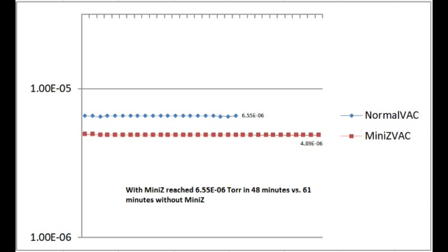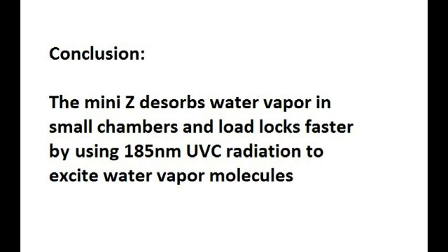Depending on your pumping, what type of pump you have, and the size of the chamber and other variables, it's going to determine what the net result is. But the conclusion is that the miniZ does in fact desorb water vapor in small chambers and load locks faster by using the 185 nanometer UVC radiation to excite the water vapor molecules, just the same way that our UVB100 product does.